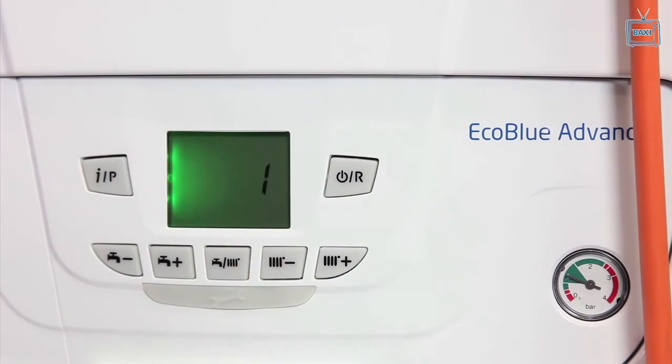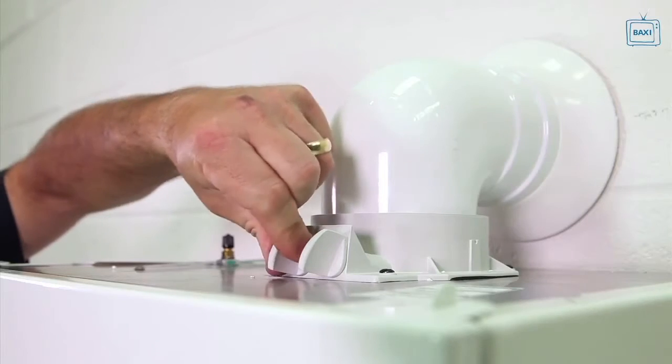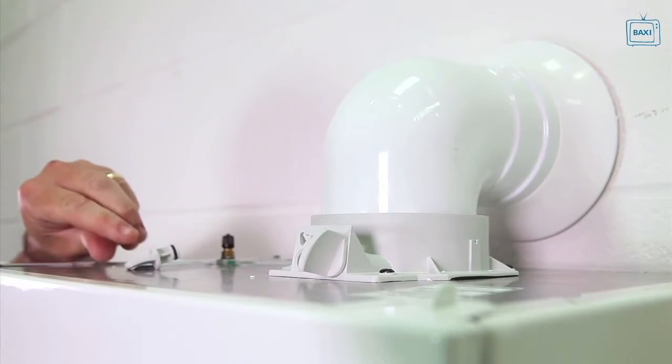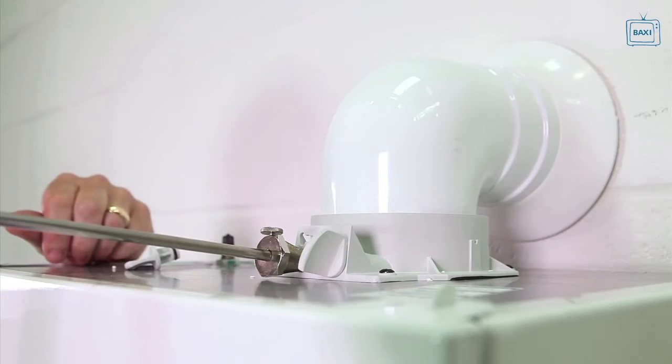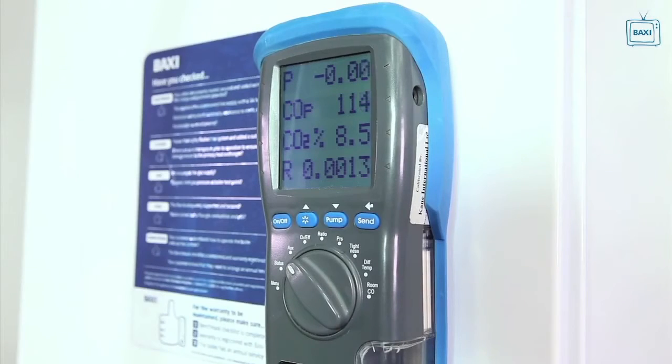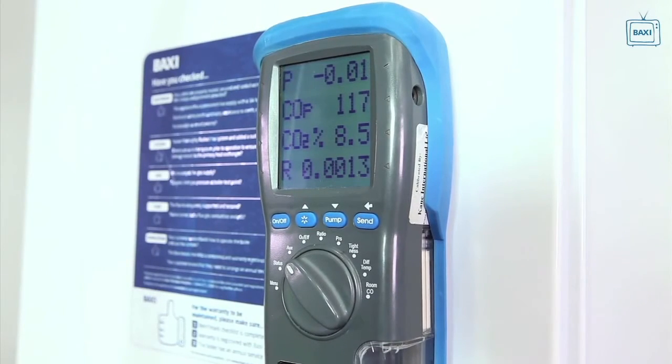Set the boiler to the minimum rate and allow the combustion to stabilise. Insert the analyzer probe into the flue gas test point, allowing the reading to stabilise. A positive check will show a reading of 8.4% plus or minus 0.2%.